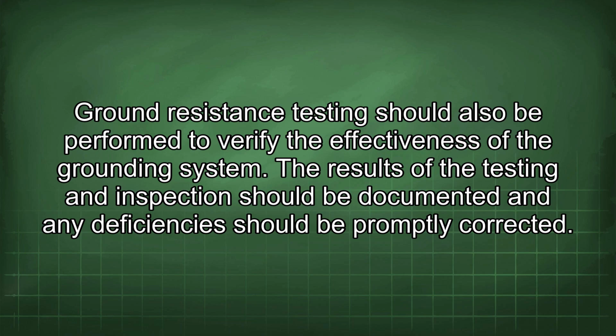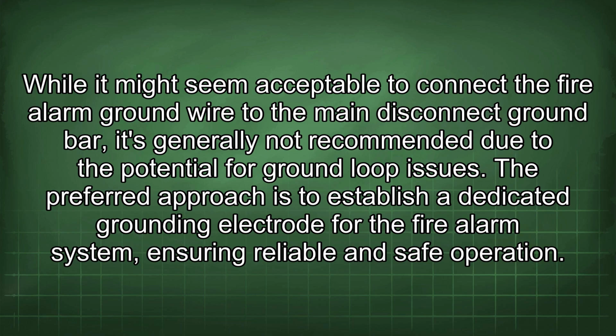Ground resistance testing should also be performed to verify the effectiveness of the grounding system. The results of the testing and inspection should be documented, and any deficiencies should be promptly corrected. While it might seem acceptable to connect the fire alarm ground wire to the main disconnect ground bar, it's generally not recommended due to the potential for ground loop issues. The preferred approach is to establish a dedicated grounding electrode for the fire alarm system, ensuring reliable and safe operation.